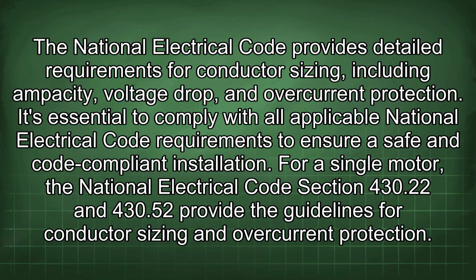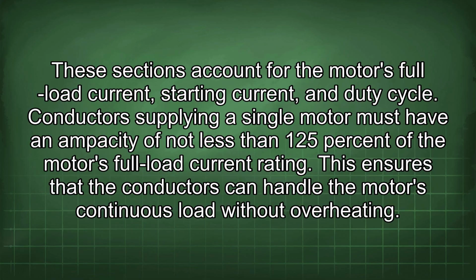For a single motor, the National Electrical Code Sections 430.22 and 430.52 provide the guidelines for conductor sizing and overcurrent protection. These sections account for the motor's full load current, starting current, and duty cycle. Conductors supplying a single motor must have an ampacity of not less than 125% of the motor's full load current rating.